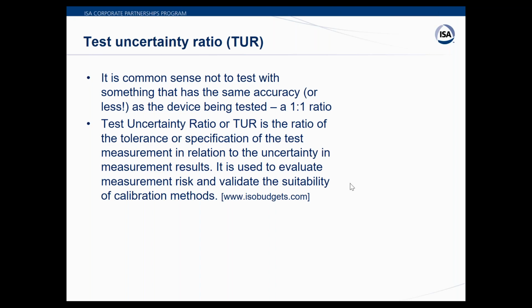So here's a definition of test uncertainty ratio. It is the ratio of the tolerance or specification of the test measurement in relation to the uncertainty in the measurement result. So we're looking at what's the ratio from the standard to the process. That's kind of a simple way to say it. And by using this as a guideline, and our first question today was exactly on this topic, it helps you evaluate how much risk you're taking. So if you're in this 1-to-1 ratio, that's a lot of risk. If you have a better ratio, your risk goes down. And by doing this analysis, you're validating and qualifying your calibration program.